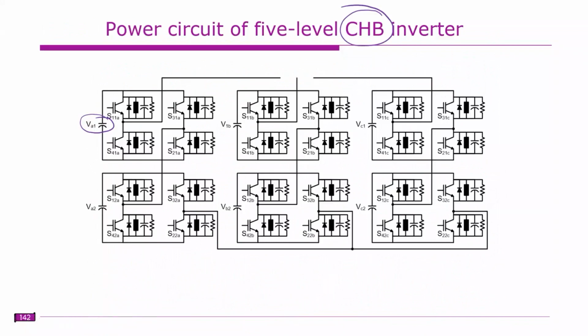Okay. So here you have the IGBT along with its anti-parallel diodes. This entire thing is for protection, right? This is the varistor, and we have a snubber capacitor, and some protective or bypass resistor will be there. So this entire thing is a snubber circuit. It consists of a varistor for sudden surges in the voltage, a snubber capacitor, and next a bleeder resistor.